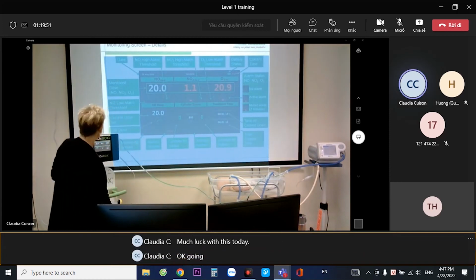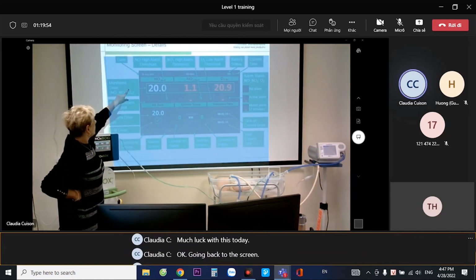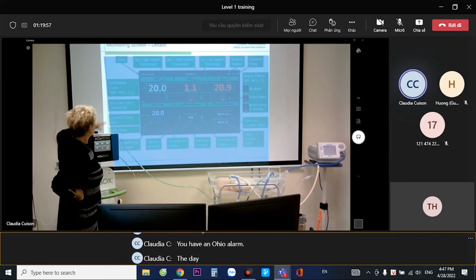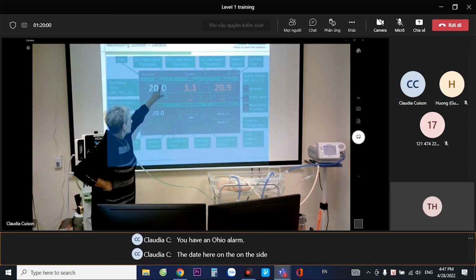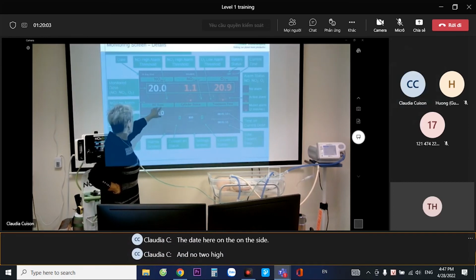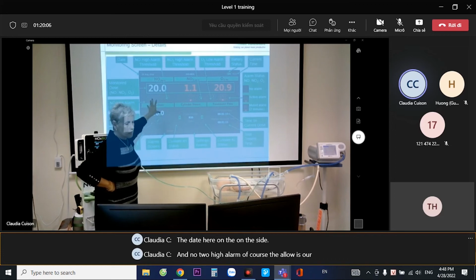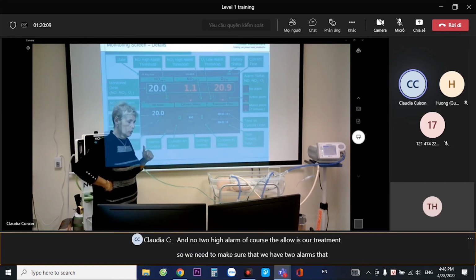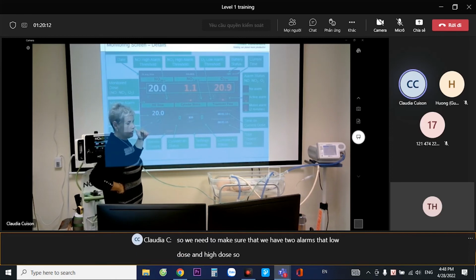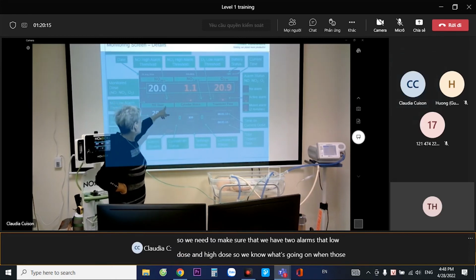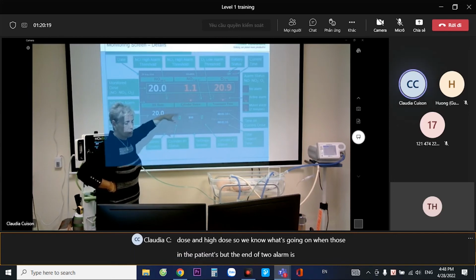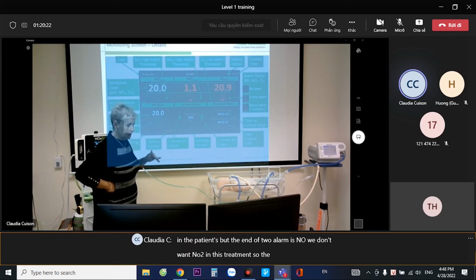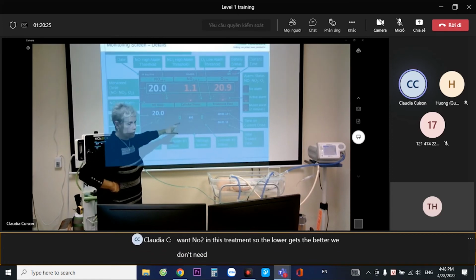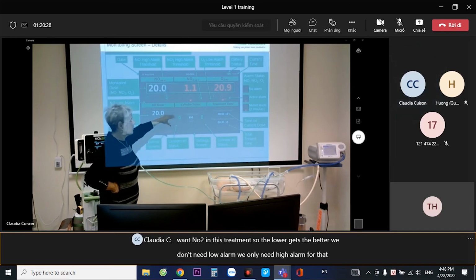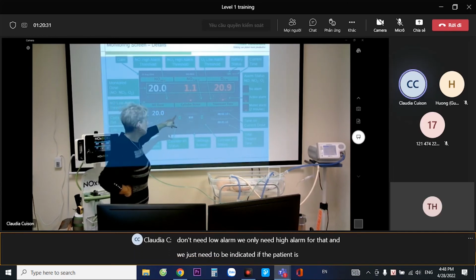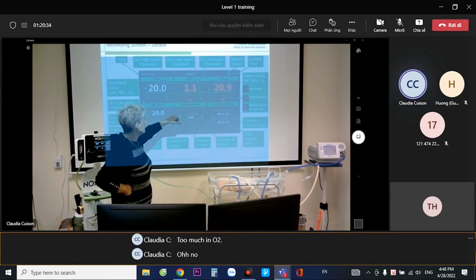Okay, going back to the screen, you have the NO high alarm, and on the side the NO2 high alarm. Of course, the NO is our treatment, so we need to make sure that we have two alarms, the low dose and the high dose, so we know what's going on when dosing the patient. But NO2, we don't want NO2 in this treatment, so the lower it gets, the better. We don't need a low alarm. We only need a high alarm for that. We just need to be indicated if the patient is receiving too much NO2 on the circuit.